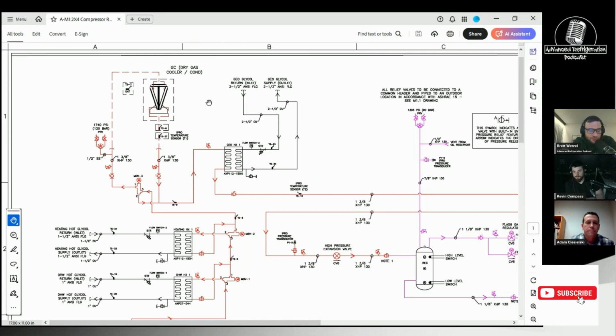Since you brought it up, because you talked about rack crashing, so Kevin and I had a discussion last week about control as far as the gas cooler fans, and we're both on the same page. Kevin, do you want to explain, or do you want me to? So I like to control the gas cooler. Me and Adam have talked about this before. I like to control the gas cooler fans off of saturation pressure, converted to temperature, and run the fans off saturation. I feel that they're more stable off saturation, and most of the controllers do a better job of controlling off of saturation versus temp.